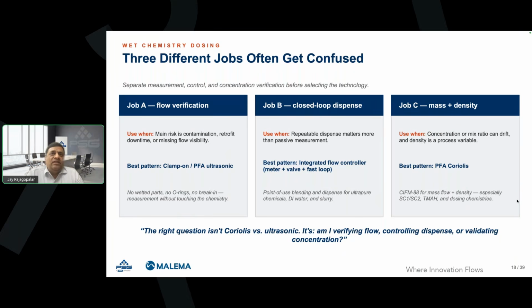In closed loop, with an integrated flow controller, repeatable dispense is critical, and here ultrasonic could be a good choice. For concentration and mix ratio, where the mass and the density play a role in mixing different chemistries, especially SC1 and SC2 type of applications, Coriolis technology is a better choice than ultrasonic and other technologies. So the right question is not Coriolis versus ultrasonic. It is where you're applying it and what is the end purpose, and you apply the technologies appropriately.